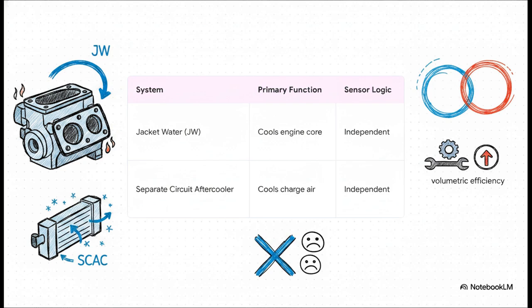Meanwhile, the separate circuit aftercooler, or SCAC, is an entirely different loop that pulls heat out of the compressed intake air before it hits the cylinders. Why does separating them matter so much? Well, the block needs stable, moderate temperatures, but the charge air needs to be aggressively cooled. Combining those two very different needs into a single circuit would force a compromise that hurts both engine longevity and volumetric efficiency.